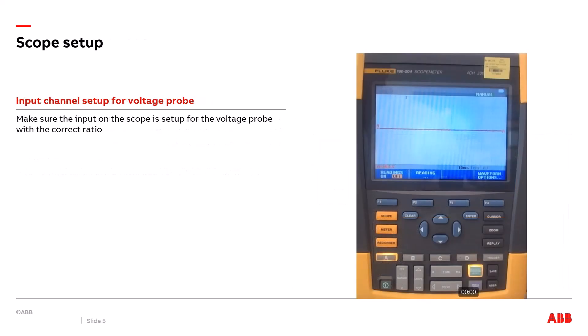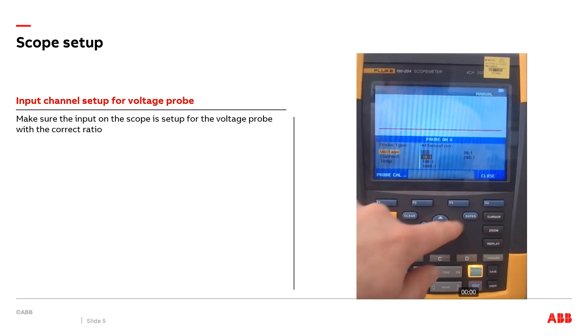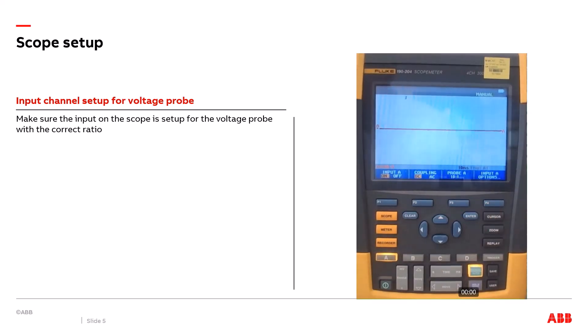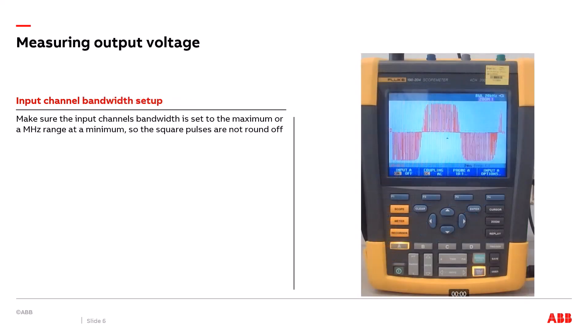Now that we have the voltage probe connected to two of the output phases of the VFD, it's time to set up the input channel on the scope for the voltage probe. You select channel A, voltage, and it's important to select the correct probe ratio. I'm using a 10-to-1 passive probe, so I select a 10-to-1 ratio. We also need to set up the bandwidth for input channel A correctly; otherwise, you could be filtering out part of the signal we're trying to measure.